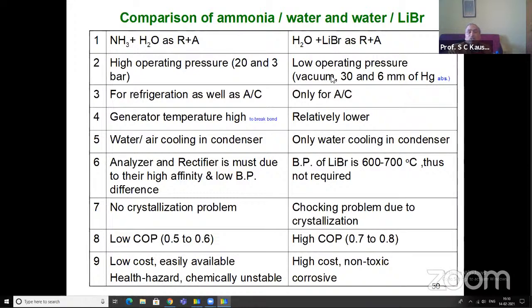Both are much lower than the atmospheric pressure, which is 760 millimeter of Hg. So we have a problem of creating vacuum in case of water lithium bromide, and we have a problem of maintaining high operating pressure vessels for the ammonia water case. But the ammonia water case is very much suitable for refrigeration as well as air conditioning, as well as heat pump operation. So that is the advantage of the ammonia.